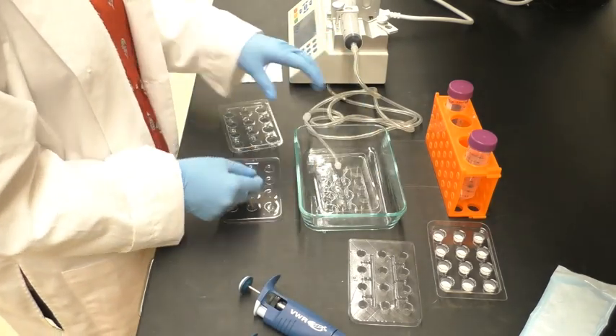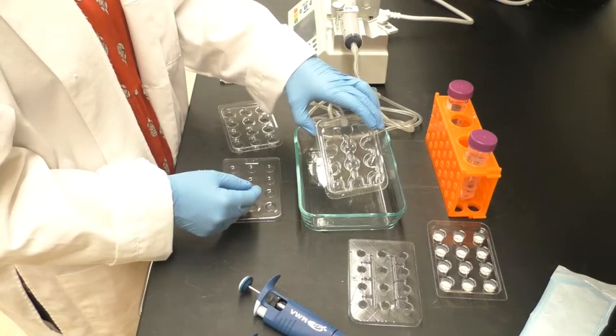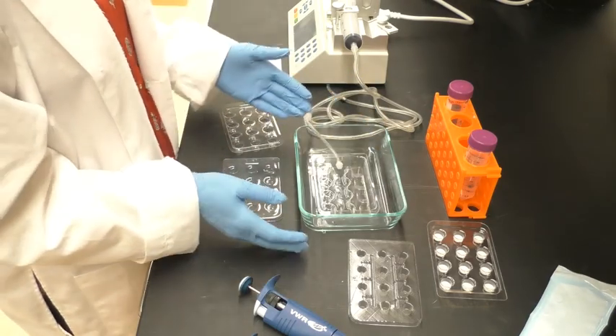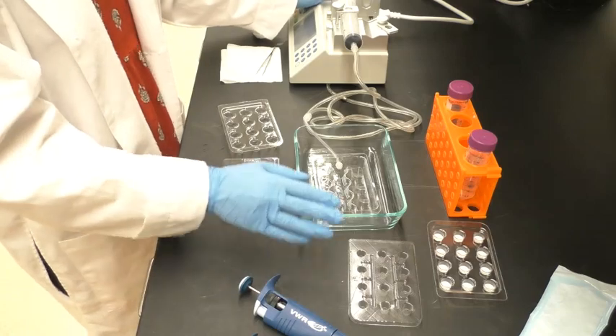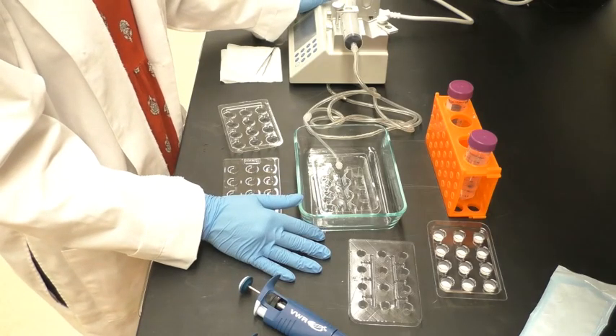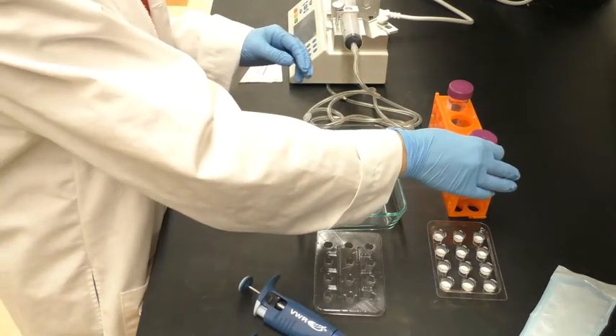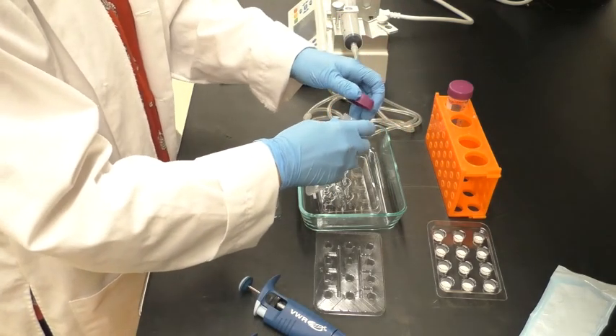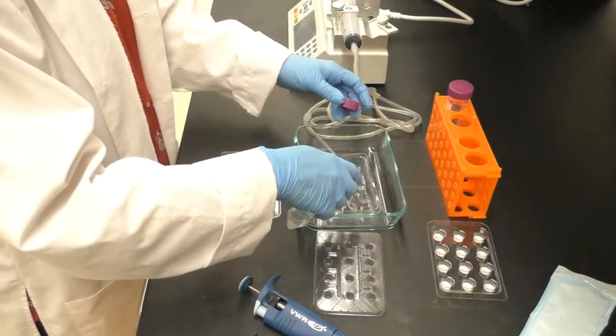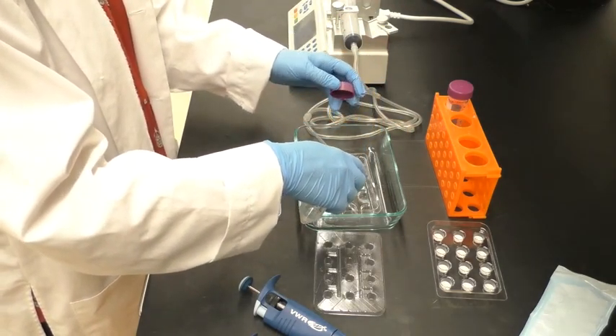First, attach one end of the tube to the PerfusionPal tray, the item that looks like a multi-well plate, and attach the lower fitting. Attach the other end of that tube to the lower fitting on a 60 ml syringe. Then place the syringe into the syringe pump. The system is now ready to be primed.